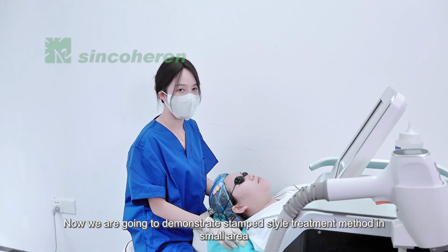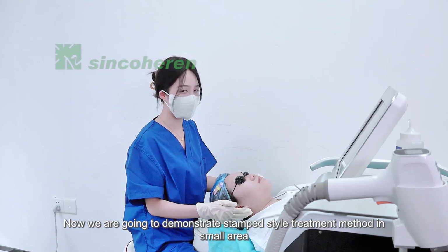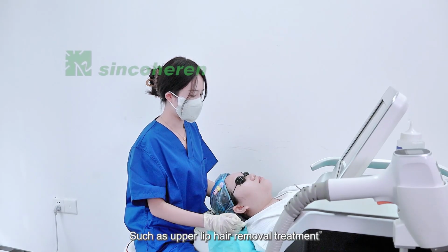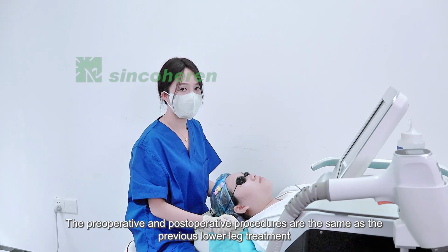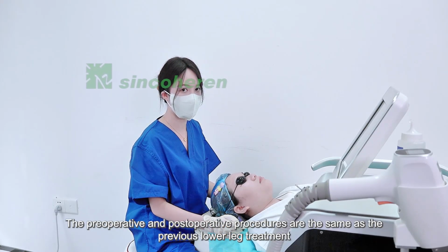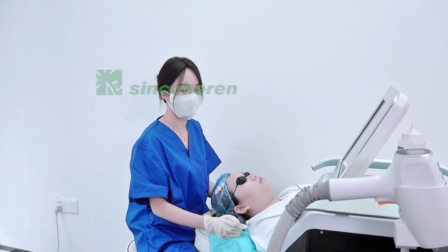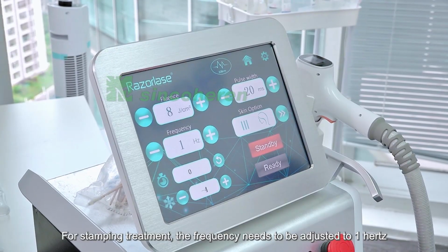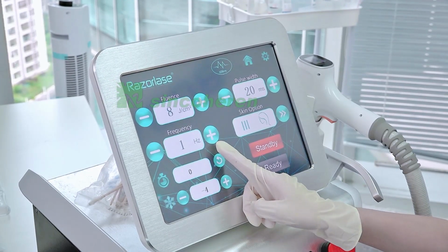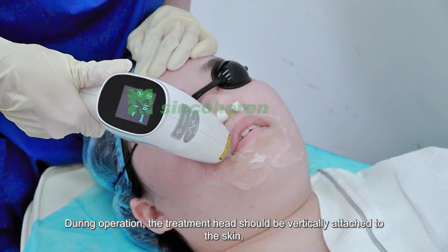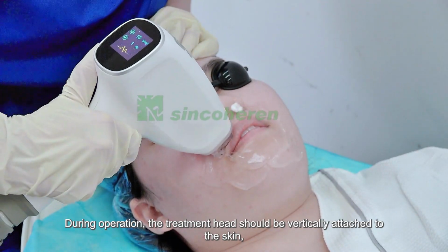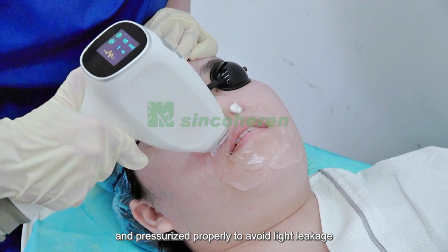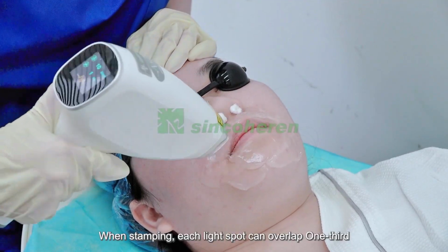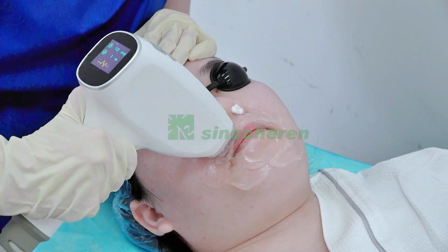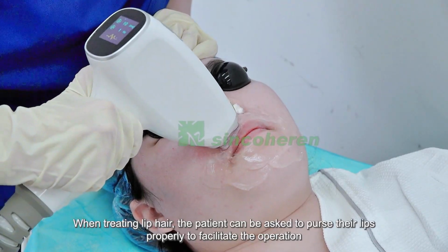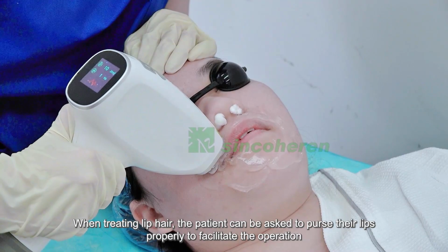Now we are going to demonstrate the stamp-style treatment method in a small area, such as upper lip hair removal treatment. The preoperative and postoperative procedures are the same as the previous lower leg treatment. For stamping treatment, the frequency needs to be adjusted to 1 Hz. During operation, the treatment head should be vertically attached to the skin and pressurized properly to avoid light leakage. When stamping, each light spot can overlap 1/3. When treating lip hair, the patient can be asked to purse their lips properly to facilitate the operation.